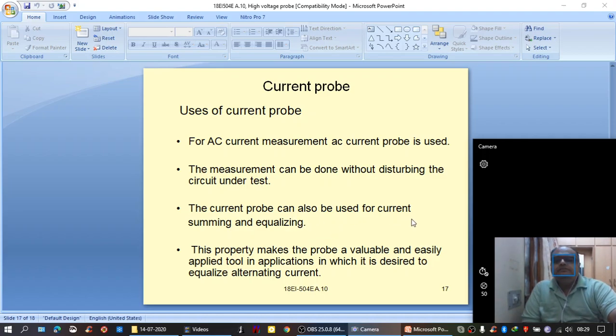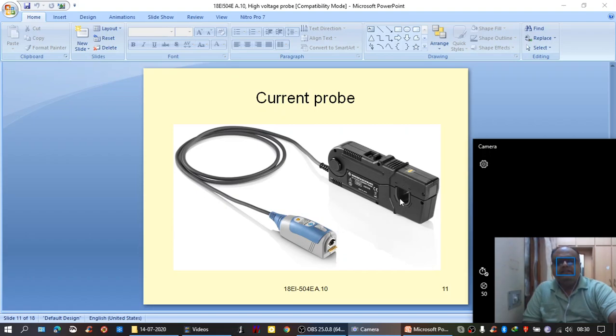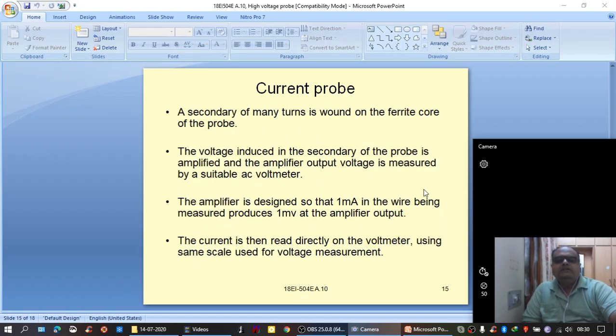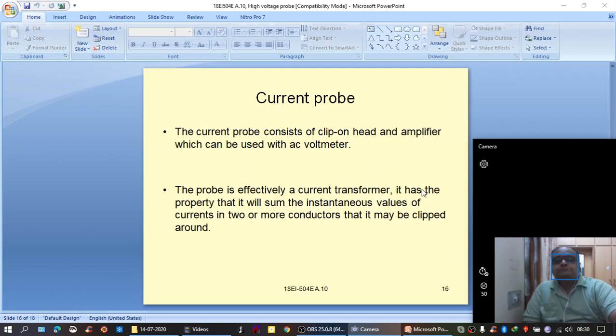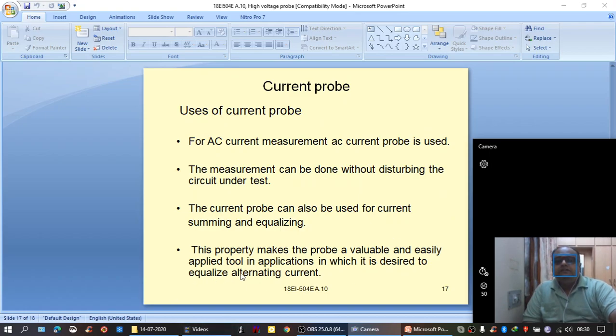The current probe can be used for current summing and equalizing also. Instead of one cable, suppose two or three cables are placed inside the same hole or ring here, then we will get a reading proportionate to the sum of the three currents or four currents depending upon the number of wires within the ring. So it is used for current summing also. This property makes the probe a more valuable and easily applied tool in applications in which it is desired to equalize alternating current.